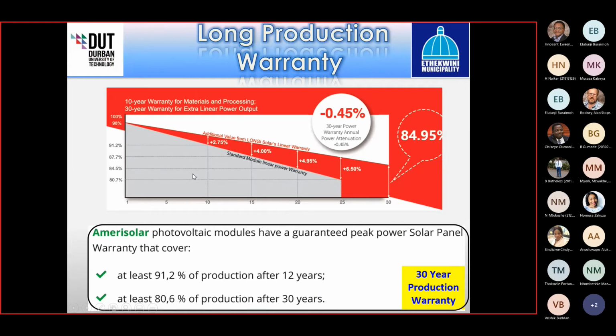There's another example from another solar panel manufacturer. So you have warranties for after 10 years, after 15 years, after 20 years, after 30 years. What's interesting is that in this panel on the top from the warranty period, after 30 years, your system will still give you almost 85% of the original production. And we can see the one at the bottom, after 30 years, it'll give you 80.6% production. So when I spoke about the sizing of the DC larger than the AC, as I said, you may get clipping in the first few years, but as the panels degrade in terms of production over time, it may counteract that effect.